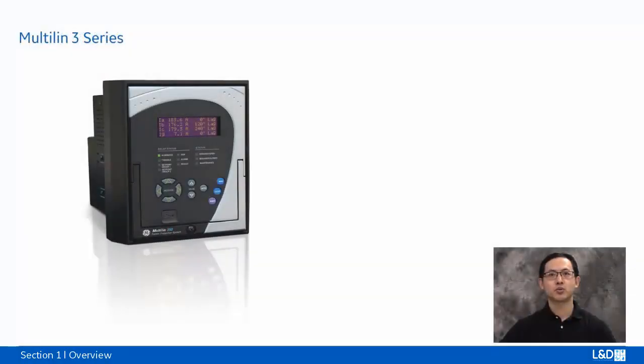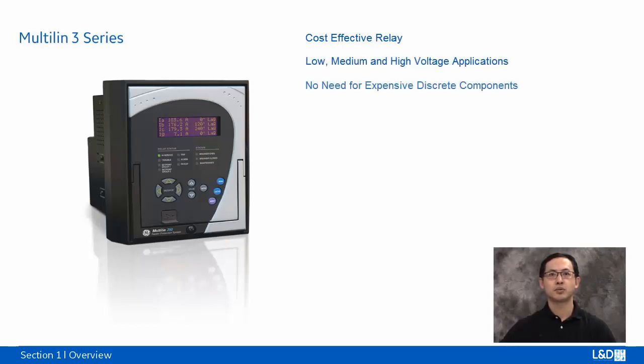3 Series Protection Relay is a highly functional, economical protection relay for utility and industrial, for low, medium, and high voltage applications. 3 Series relays effectively eliminate the need for expensive, discrete components. 3 Series relay has 3 types of relays for the protection of feeder, motor, and transformer. 350 can also be used in capacitor bank protection.